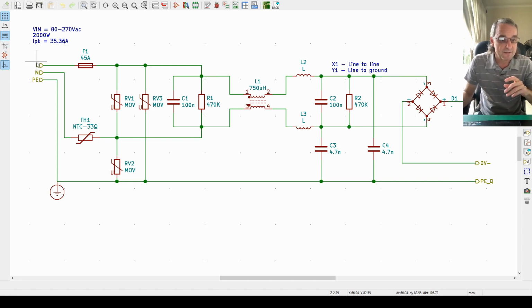So basically our line comes in through a fuse, a 45 amp fuse. We have some MOV protection, basically line to line, and then each line to earth. All the MOVs are there for any sort of surge, transient noise, whatever. They will shunt that back to earth, to the primary earth. So any transient noise that comes through, all these MOVs are doing is shunting that transient or noise back to earth.